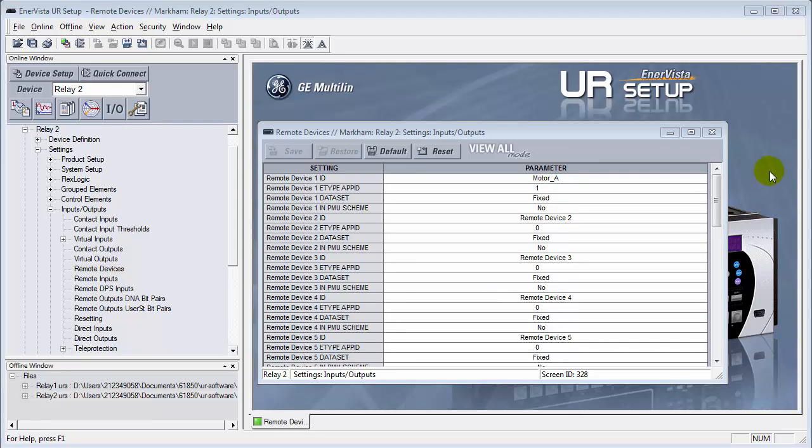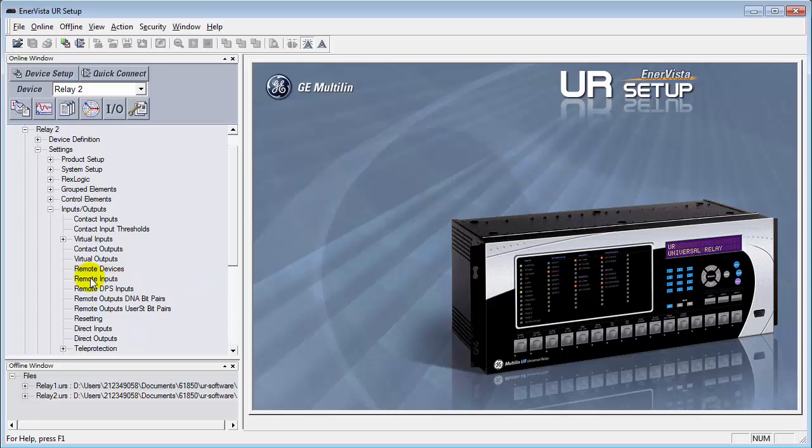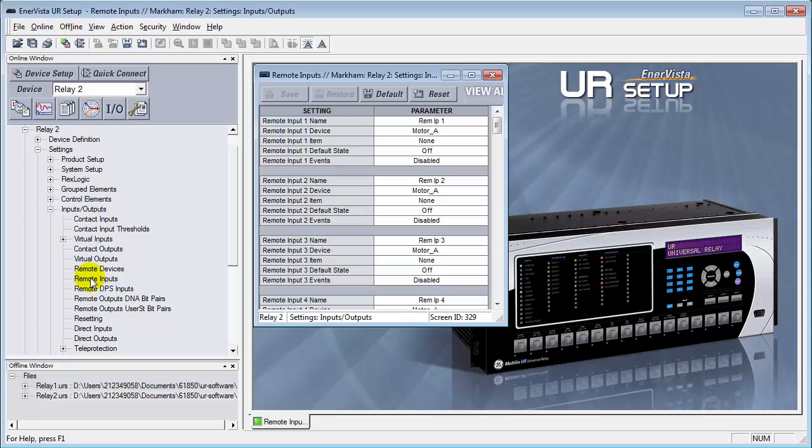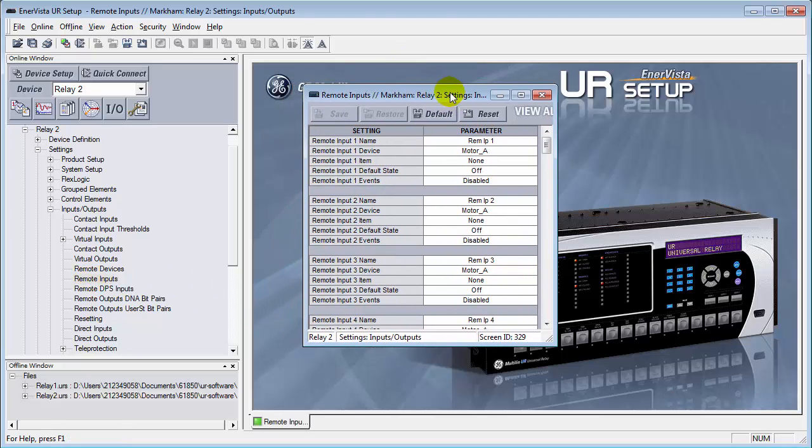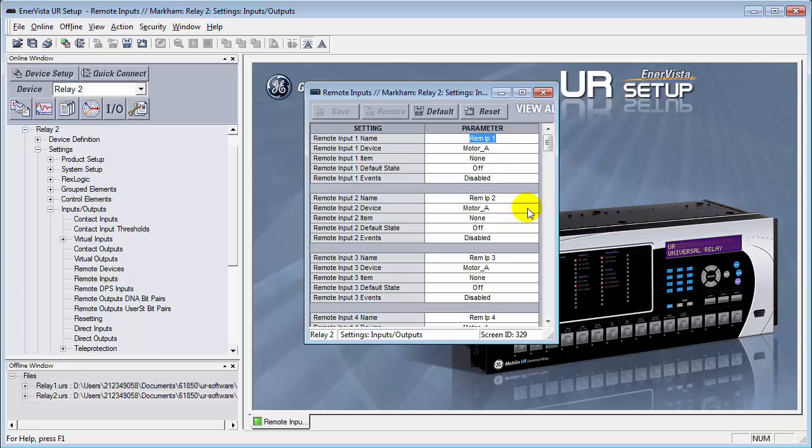The next thing that we need to do, we can close this now, is go down to our remote inputs. And in here, we can go in and actually give the name of the remote inputs that we're going to be dealing with. We can call this, let's say, breaker1 52A, just to give it a name. Beside the device, it will list the different goose messages that we're going to be looking for, that we're going to be subscribing to.